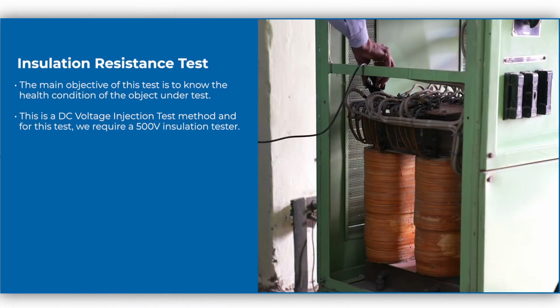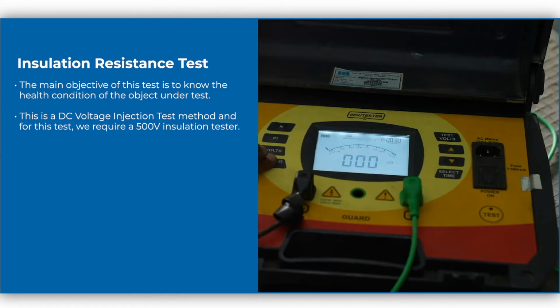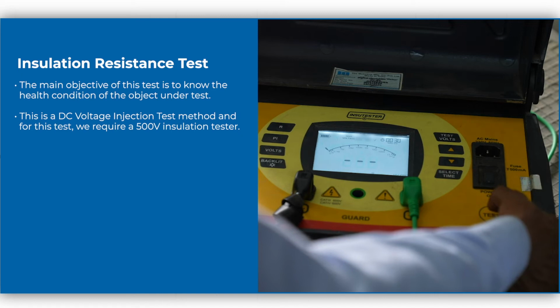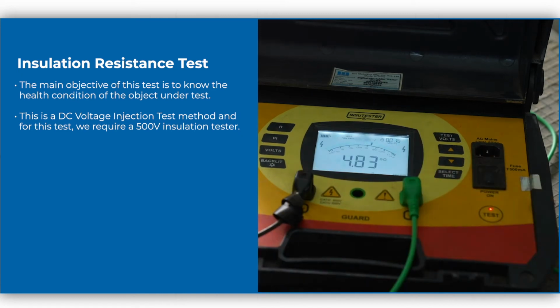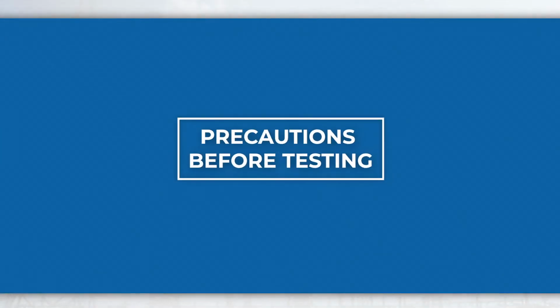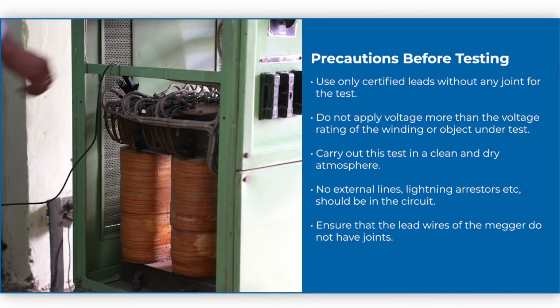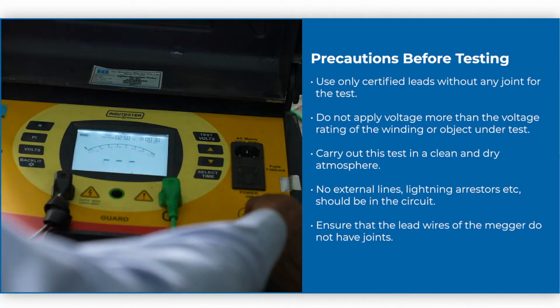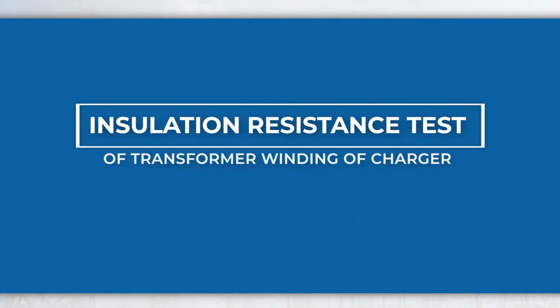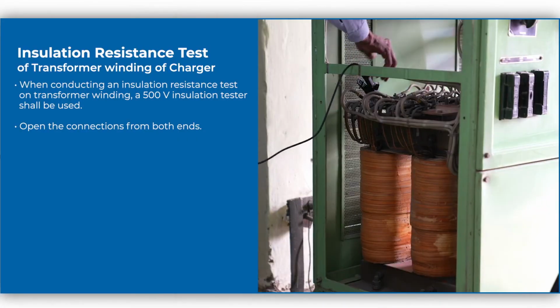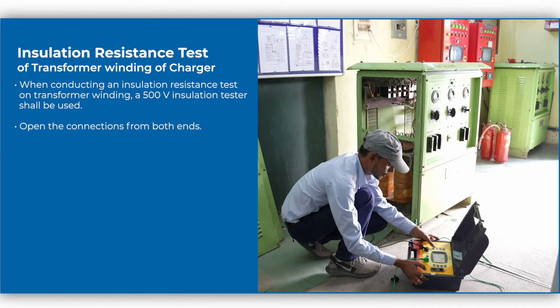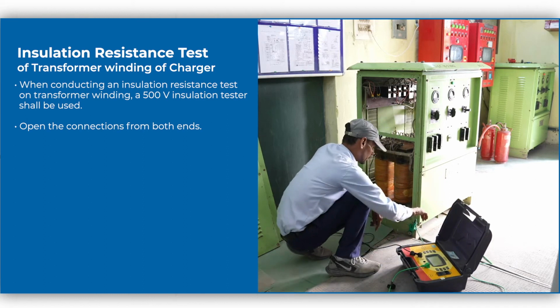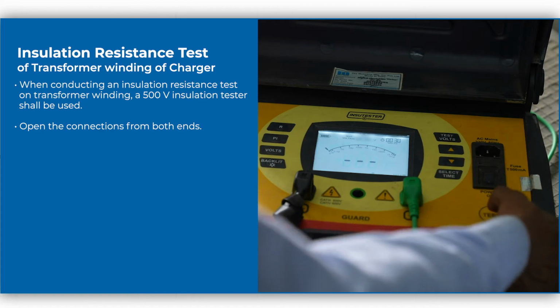Insulation resistance test. The main objective of this test is to know the health condition of the object under test. This is a DC voltage injection test method, and for this test we require a 500 volt insulation tester. Precautions before testing. While performing the tests, the following precautions shall be ensured. Insulation resistance test of transformer winding of charger. When conducting an insulation resistance test on transformer winding, a 500V insulation tester shall be used. Open the connections from both ends.